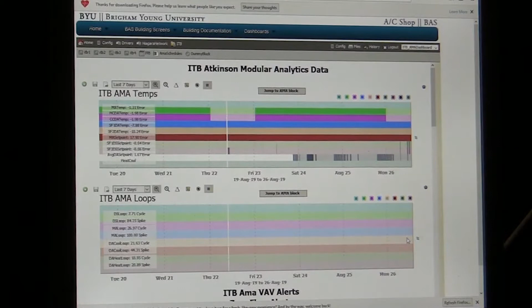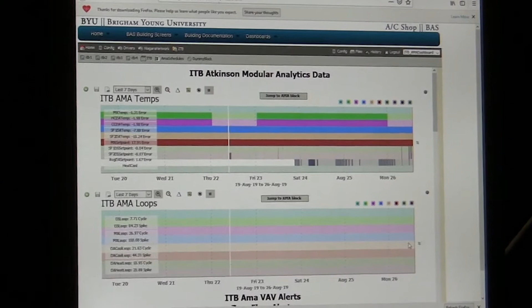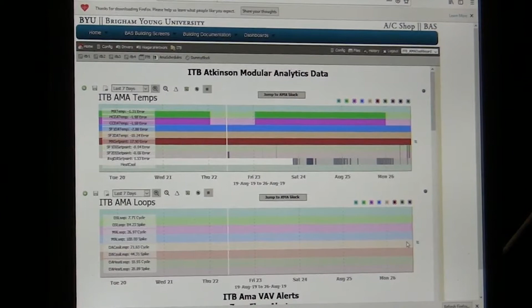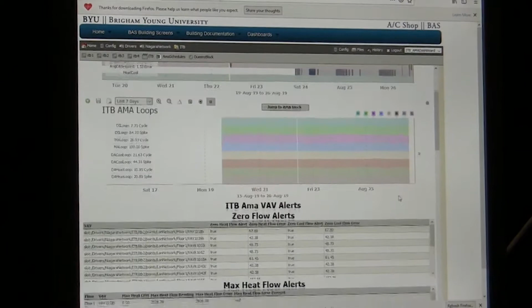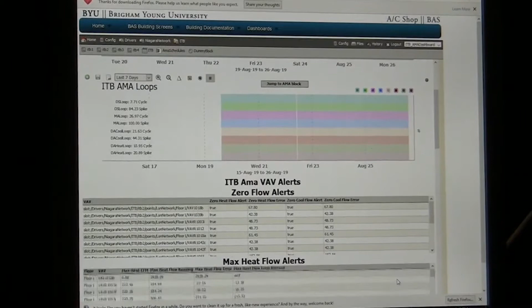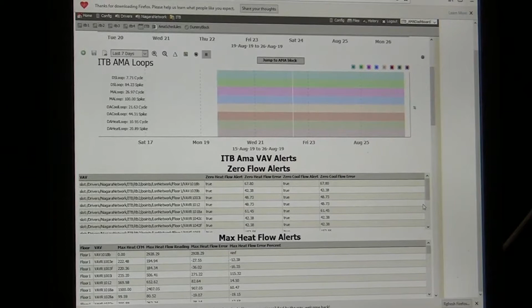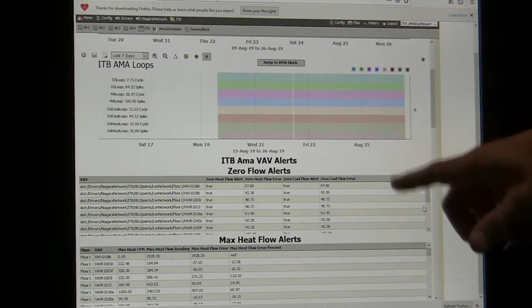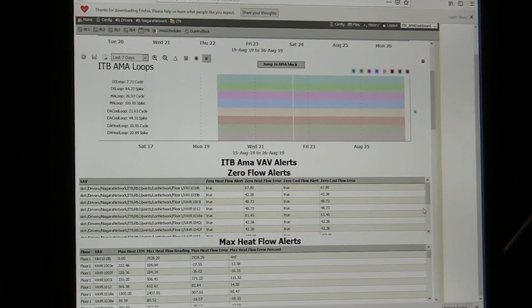In the case here, we probably have a chiller still running when we think it's not, and the chilled water valve is not shutting. And that's probably what's causing our sensor issue. Okay, but that's one of the things that we can use analytics to find, to make sure everything is working correctly. There are some other analytics down further where we look at, let's get this one back up, boxes that have zero flow alerts. We tried to zero the box during the night, and if it didn't get to zero, then we put a little flag on it saying, hey, the box isn't closing. We do the same with the max heat and cooling and check those. And so it's kind of a list of things that, hey, here's the big issues in your building that if you've got a minute, go tackle these before somebody calls and complains. Okay? It's kind of a proactive approach of trying to find problems in a building.